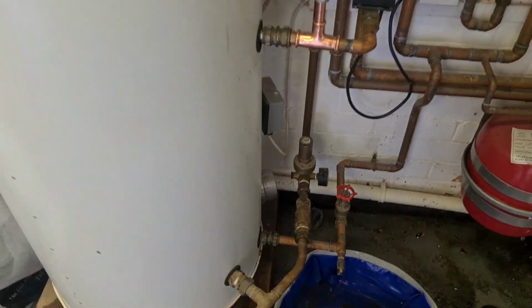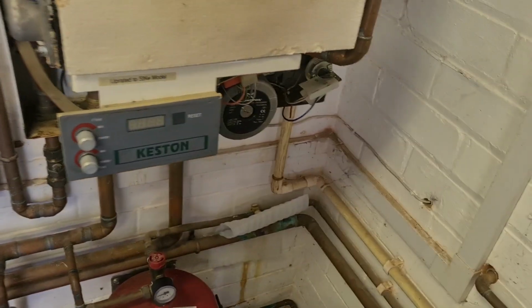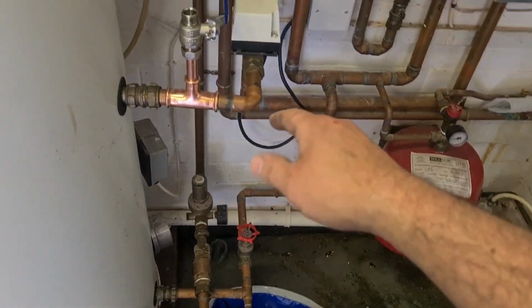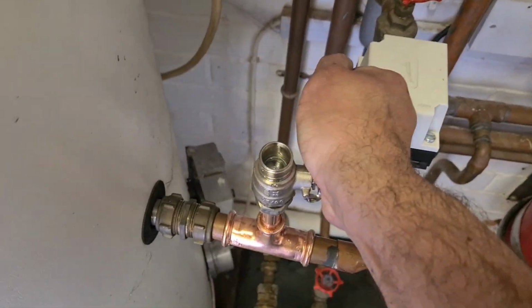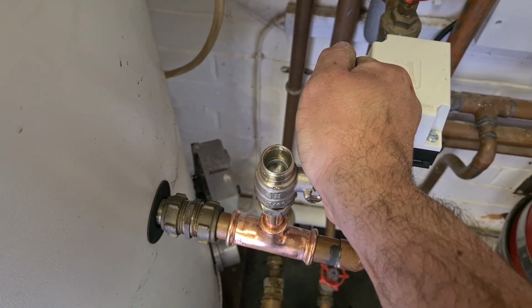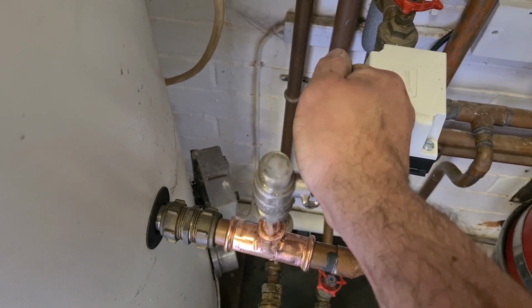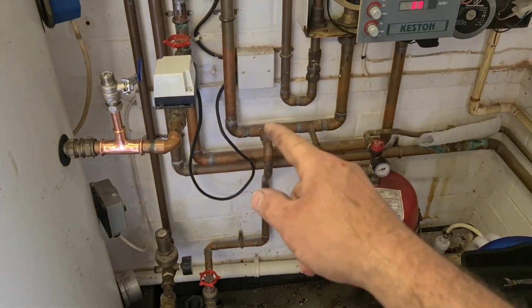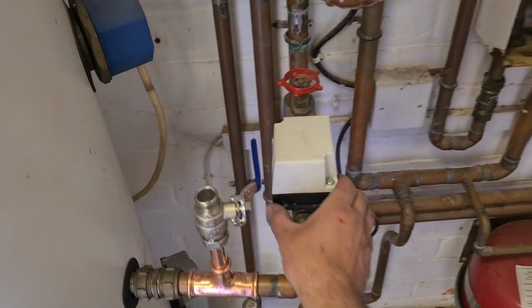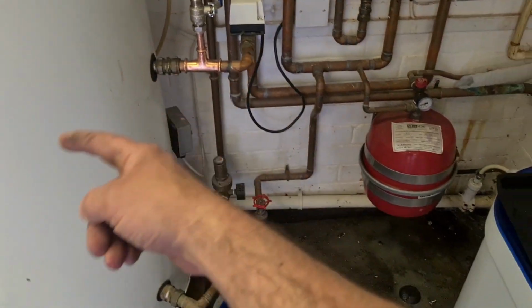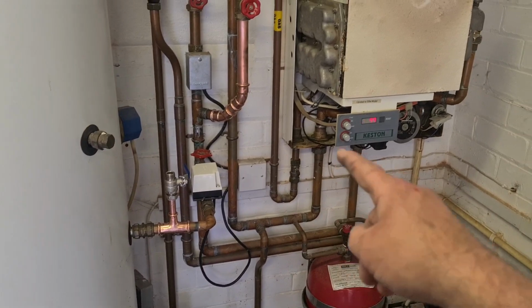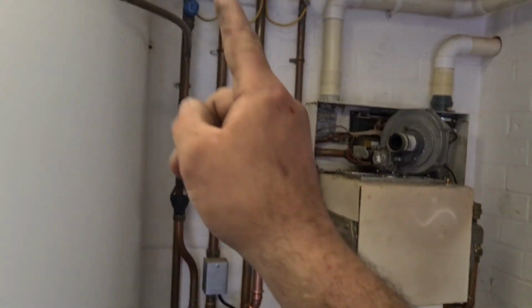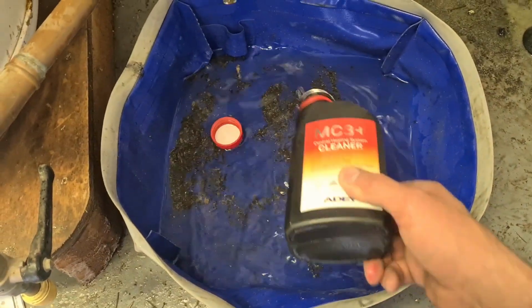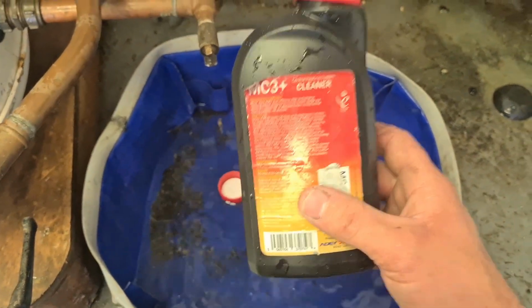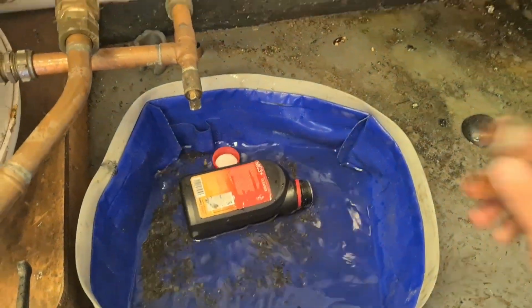So now I've introduced that into the coil, I'll get this back on full flow, boiler back up and running, and again just bleed a bit of air out there if need be. Just full now - so what will happen is I've got them open on full flow basically. If that's live, which should be turned on, which it is, that will pull that chemical in, back through the return, through the boiler, come back out from the flow and get sent around the full system. So again, just trying to work a little bit smart and think for the next visit. It's not the strongest stuff out there, but it'll do the job on this occasion, just to make the system better as we can - worth a try.